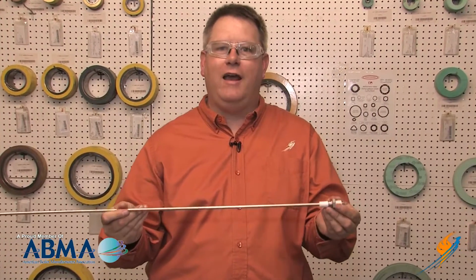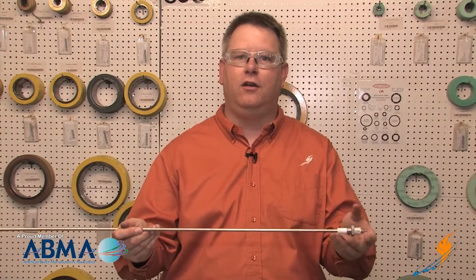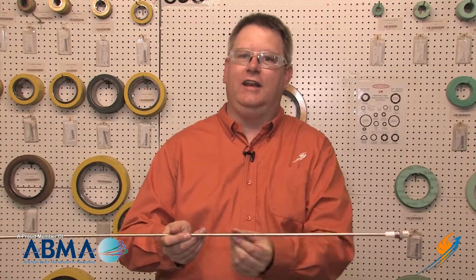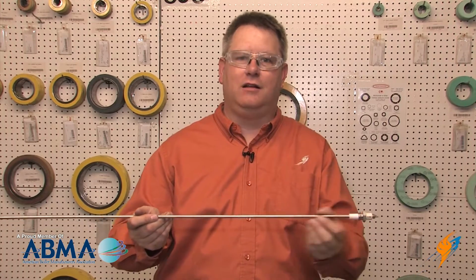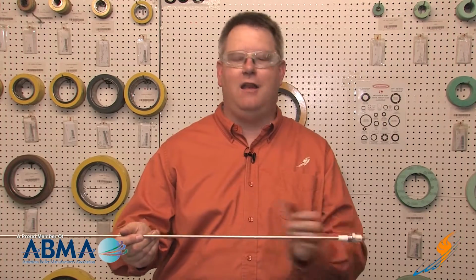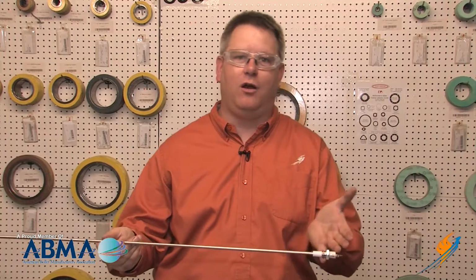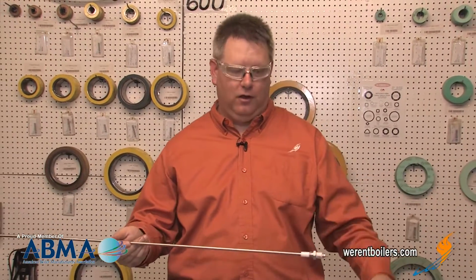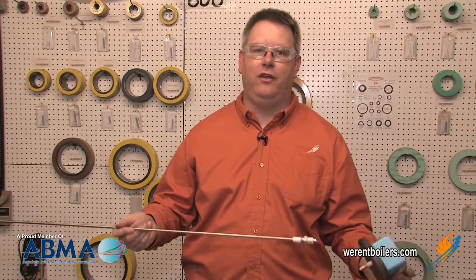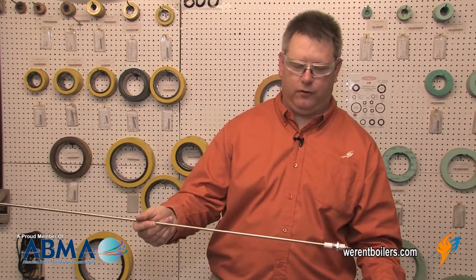One great way to find that out is during your open and close for inspection. Remove the probe, clean it, check for pitting, maybe clean it with sandpaper, and measure it. And you can actually take a Sharpie, write that measurement down on the jacket of your boiler right next to the probe housing, and then you'll have that for the future.